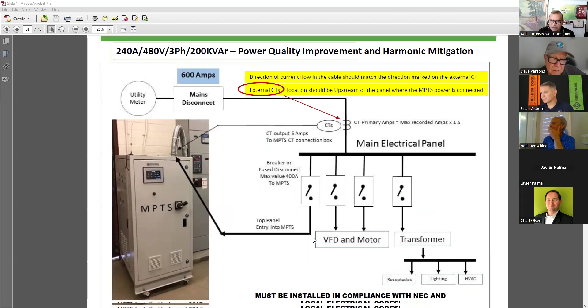You see there's a 208 volt transformer here, 480 volts coming in at 600 amps. There's a pumping station, and they have a transformer to keep this room clean, full of VFDs. One VFD already blew, which is why they put an MPTS in to protect the other one, because it's a 3,000 feet deep well motor - they cannot afford for it to go down. They already lost the redundant motor and that VFD is gone.